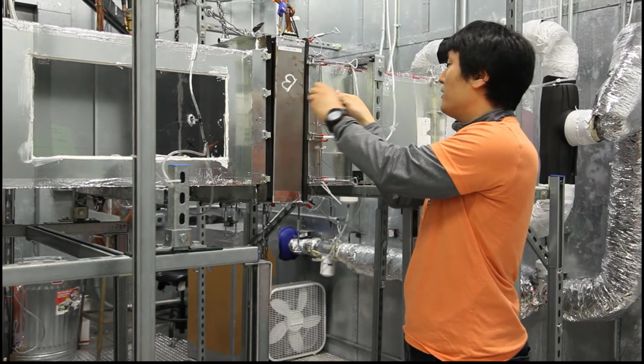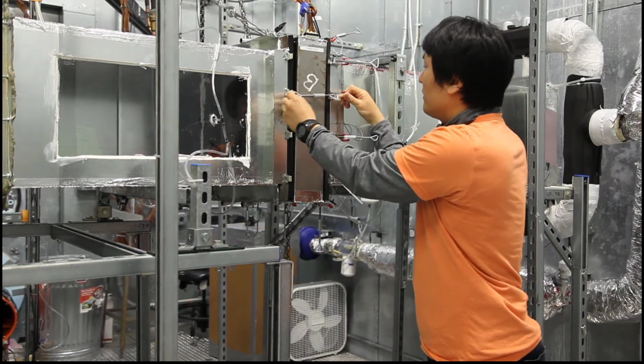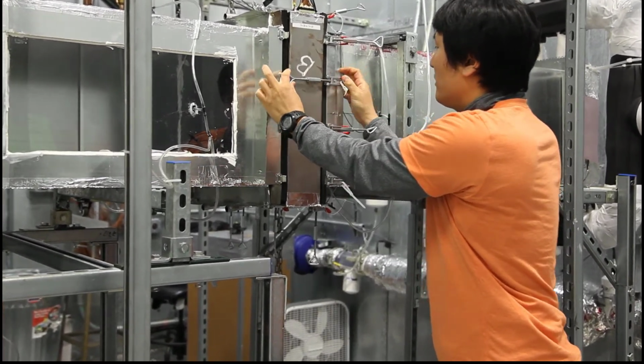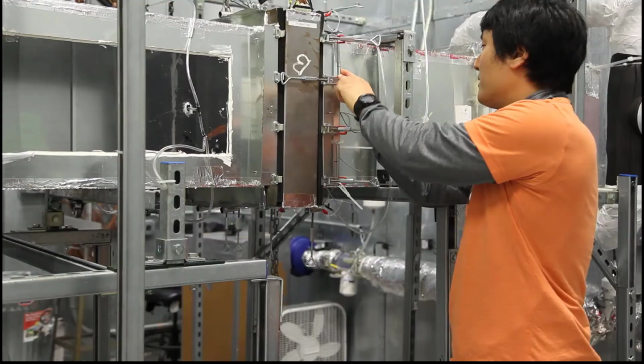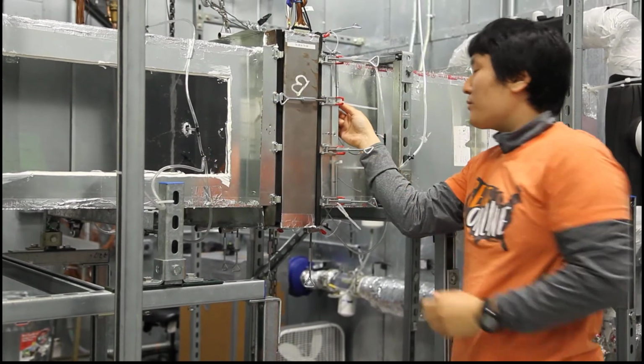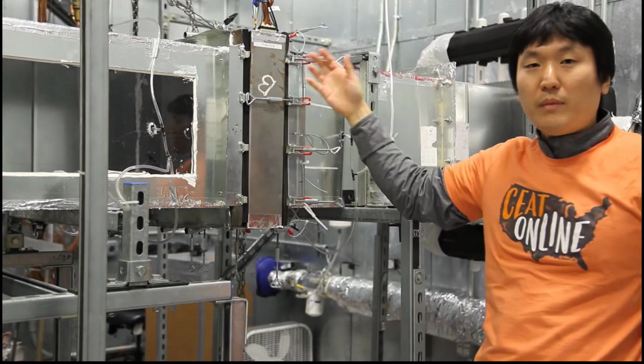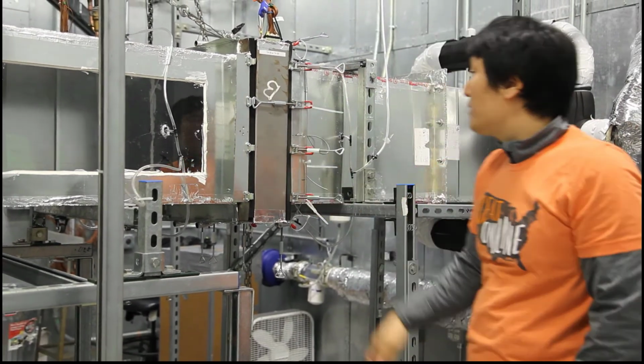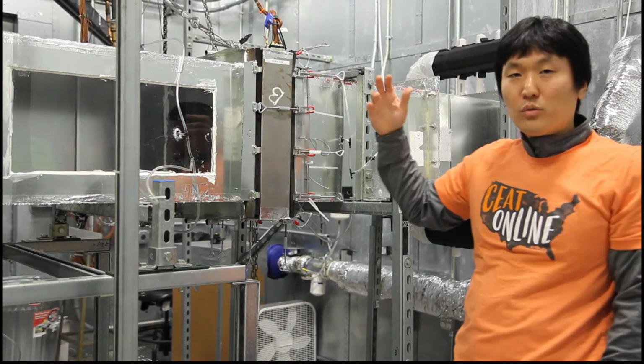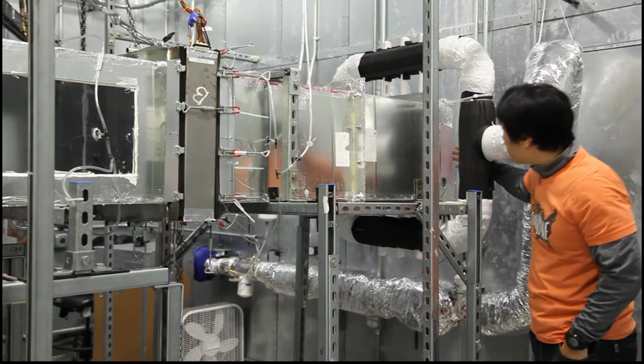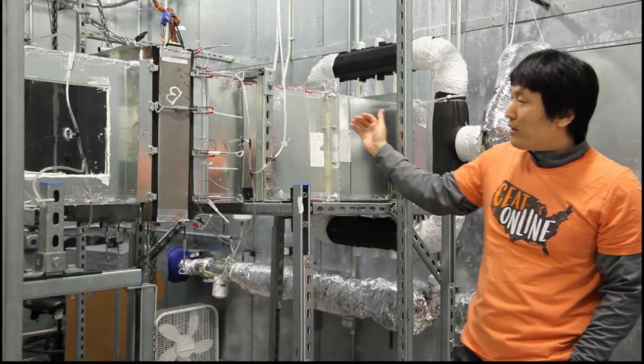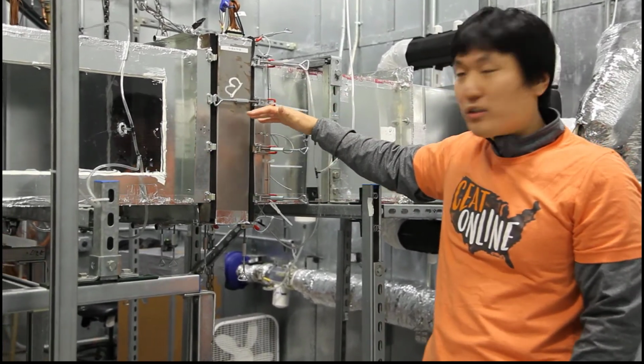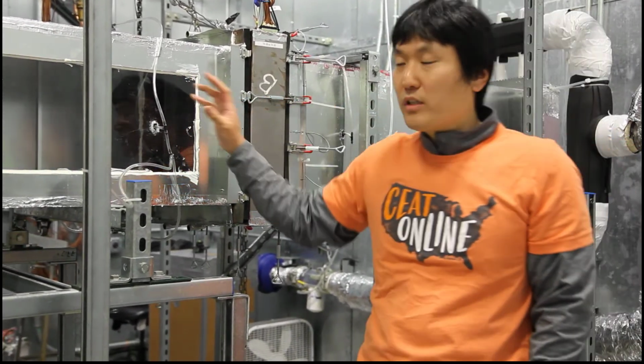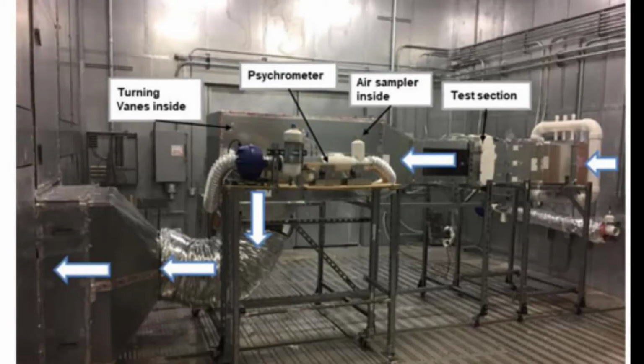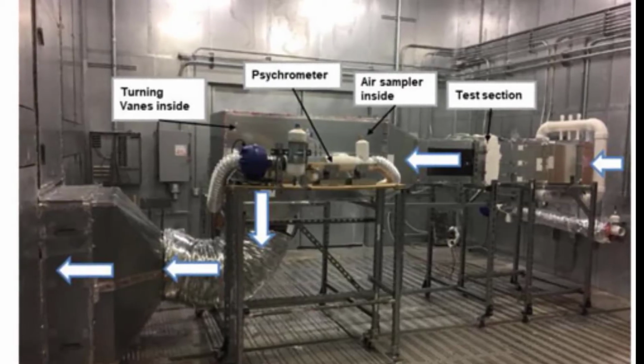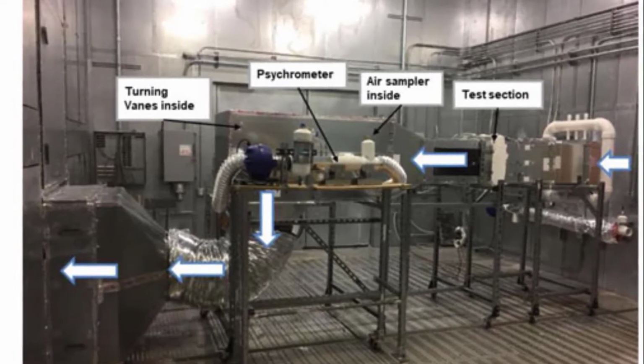connected using quick clamps. So by doing so, we can make it airtight. So the airflow coming from the inlet duct and then going through the heat exchanger module.